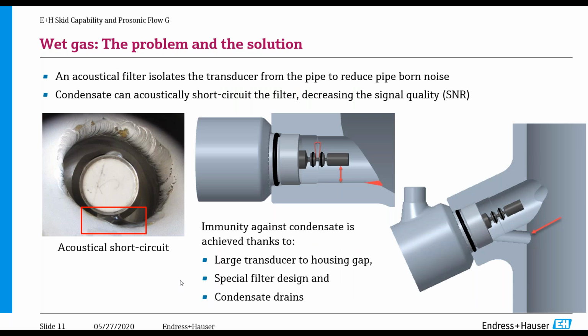As far as wet gas and some of the features that we put into the meter to overcome the difficulties in applications, you'll see on the left side, this is one of the problems that happens. We have these filters and we're trying to keep noise away from the system. On the left side, you can see that we've bridged a transducer with some liquid in there. What happens is you can filter as much as you want, but now the ultrasonic signal, if it's in the meter body, is short-circuited right directly into the transducers, and you don't want that. It's what we call bridging.